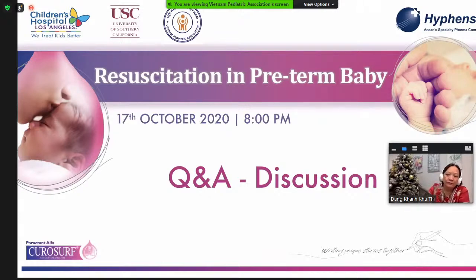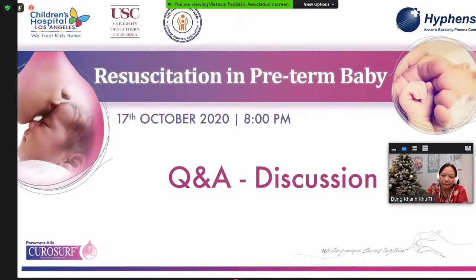If the baby's chest is not moving and the heart rate is not coming up, you could increase the PIP by turning that yellow button to 25 or a maximum of 30. Do not increase the flow rate. If you increase the flow rate in the middle of resuscitation, you will significantly increase the CPAP pressure or PEEP. So just adjust the yellow button to go up on the PIP limit from 20 to 25 or 28. The main thing is your finger, and do not hold the finger for too long. That is the inspiratory time. So even if you count one-one-thousand, that's 1 second. Take it off immediately. Put the finger down, take it off. Put the finger down, take it off. Don't hold it there, or you will end up with a pneumothorax.